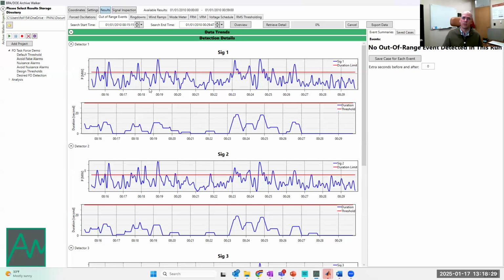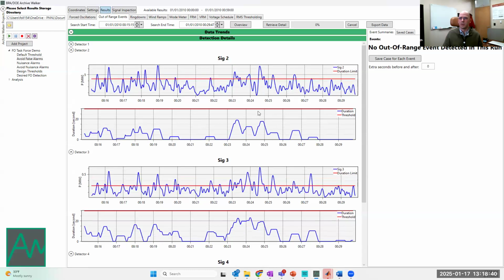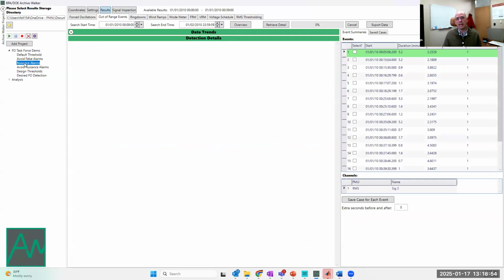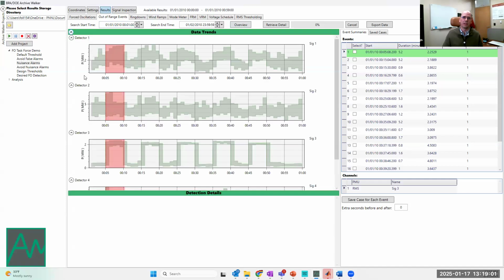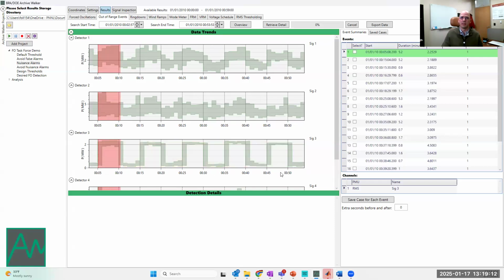And just really quickly, for each one of these signals, they're low enough that the threshold is being crossed some, but not for 30 seconds. So no false alarms here, no false alarms for signal 2, no false alarms for signal 3, and so on. So using either of the approaches that I just described, you can pretty effectively avoid false alarms. But this is where we need to start thinking about nuisance alarms, because practically, if you're operating a power system, you don't want to be notified about every little oscillation. So it's not enough to just think from a statistics perspective where you can do the theory for false alarms. It's important to be practical and also think about nuisance alarms.